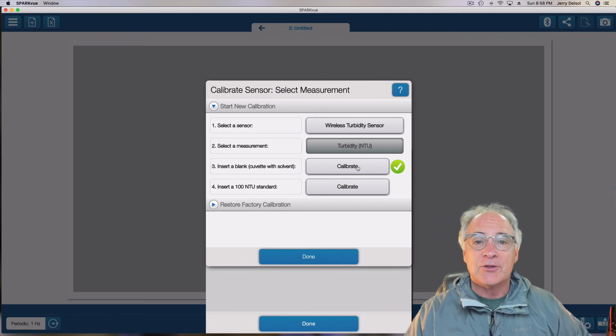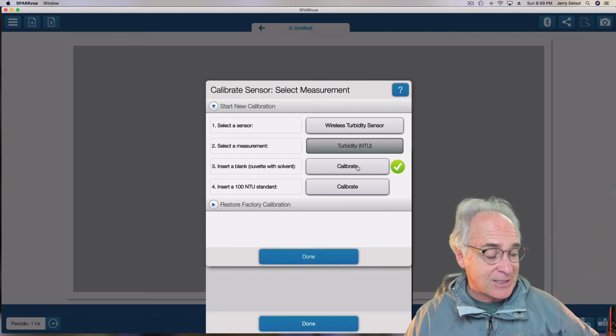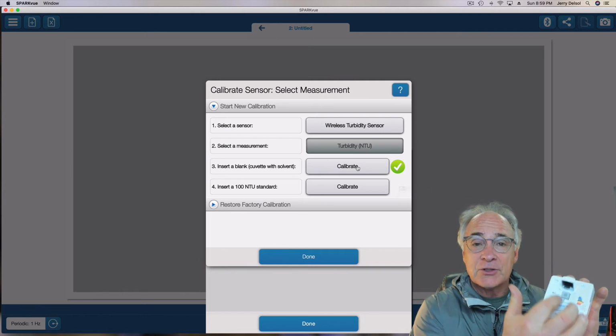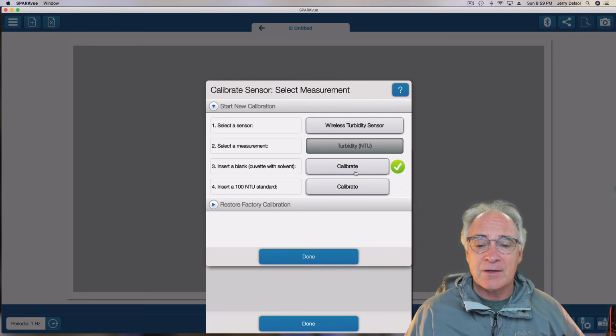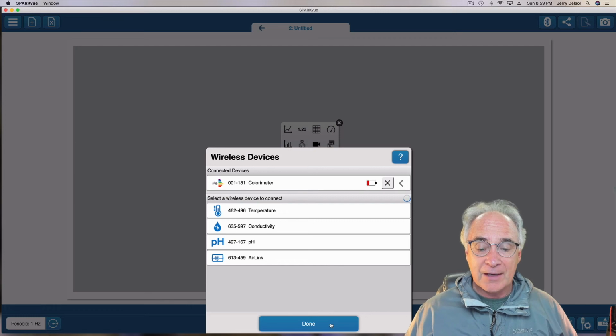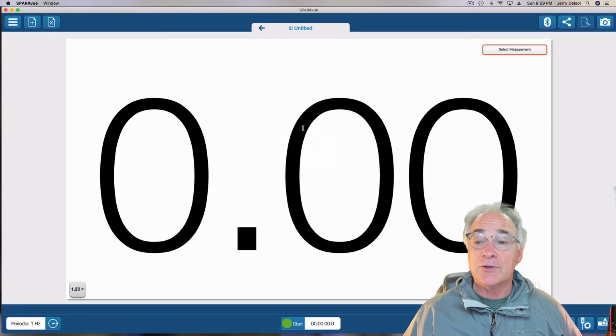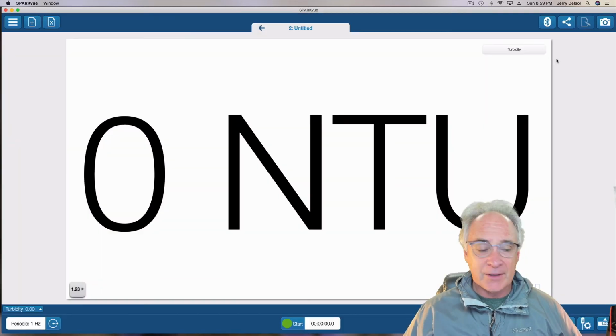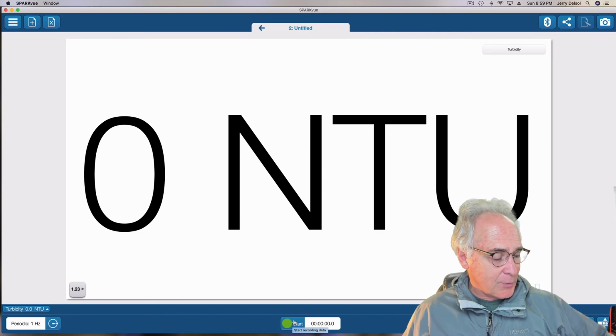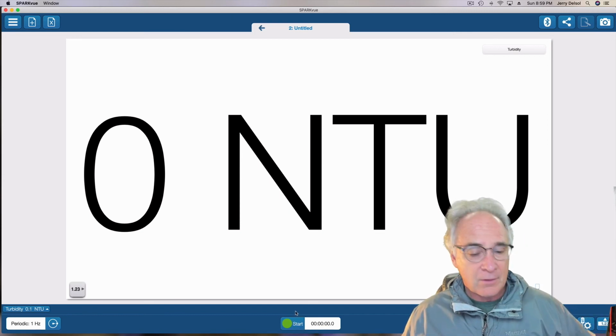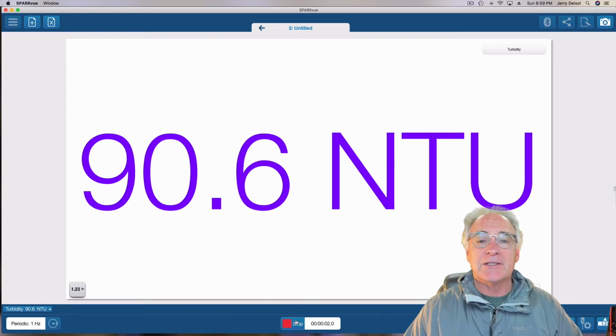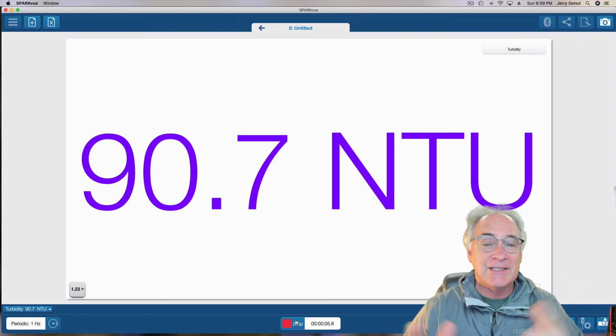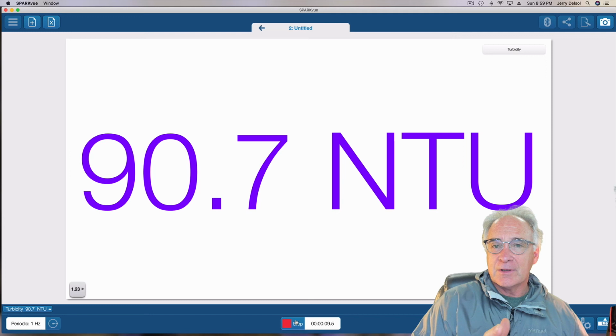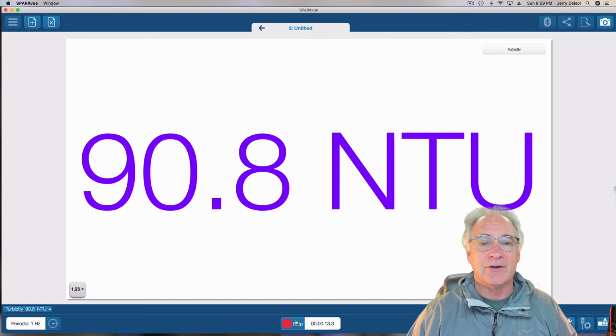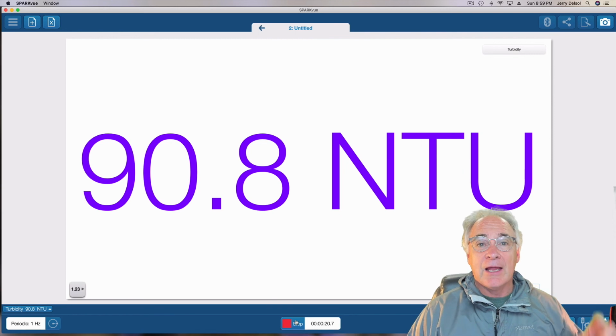So what you're going to do with that one, you're going to put it in the vial again, and then what you're going to do next is the same thing. You're just going to put that in there with the clear surfaces next to the LED, shut it, and then calibrate it. Once that's done, you're done with that. So now you can go ahead and select 1, 2, 3, select the measurement, click on turbidity. And now if you wanted to actually do that, I'm going to put the water sample in, and click start. And it's around 90 NTUs, basically on the clearer side of the 100 standard. So go ahead and finish up your samples with that. And again, thank you so much for watching, and we'll see you in the lab.